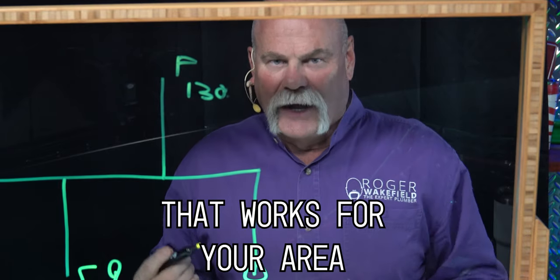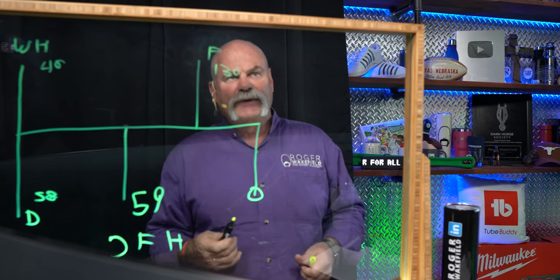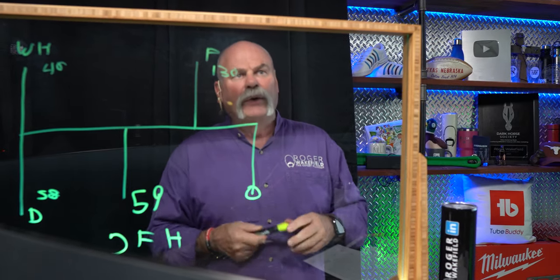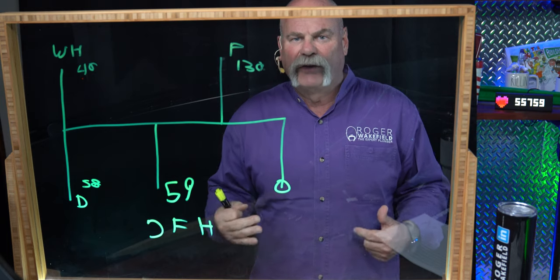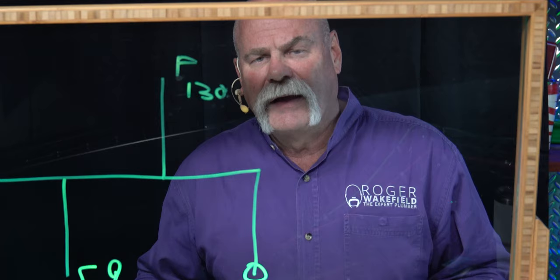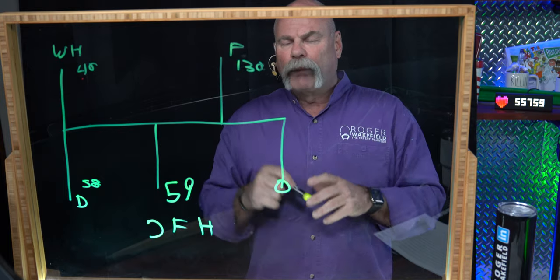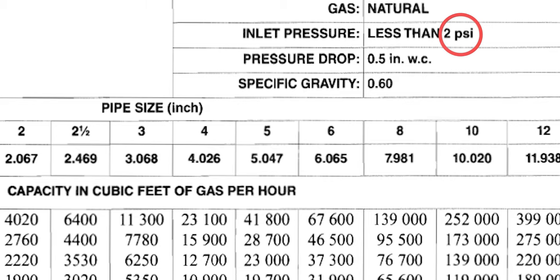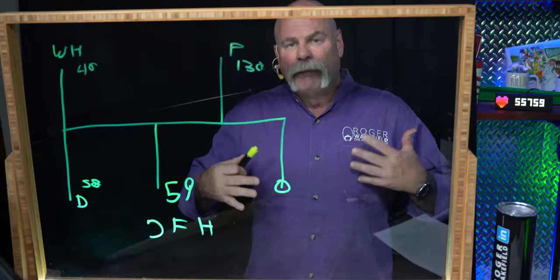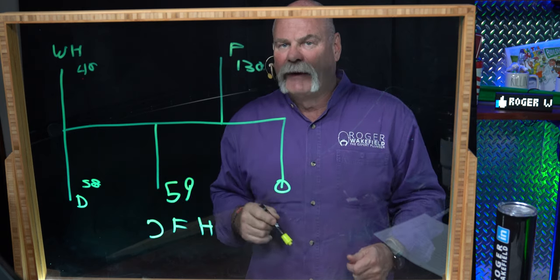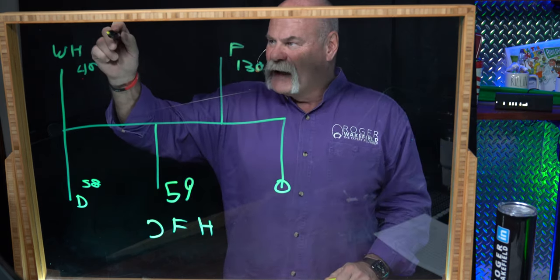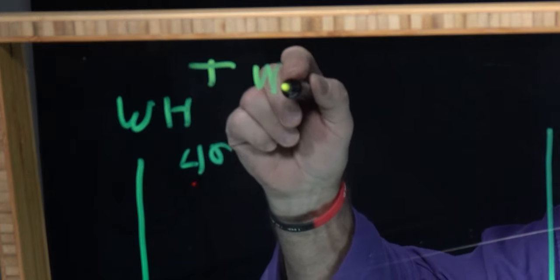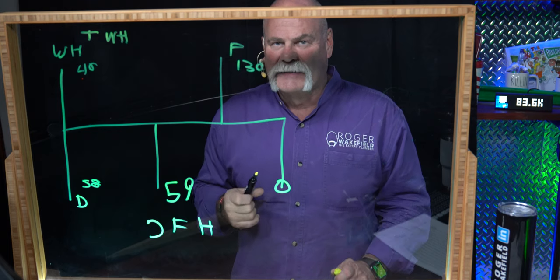There are different charts out there — look at the chart that works for your area, the one you're supposed to go by, and check the fuel gas code. Make sure you're doing everything based on the pressures you have and the pressure drop you have. What I'm going off of today is 2 PSI with a half-pound pressure drop. That's pretty conservative, but that's what I'm building this out on.